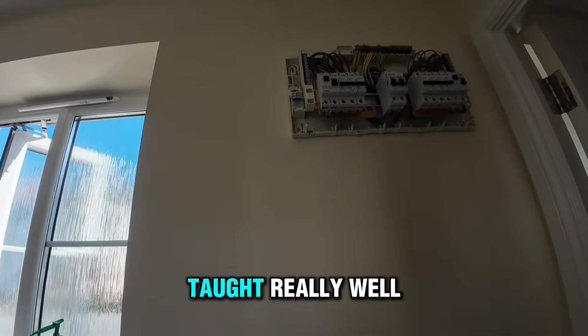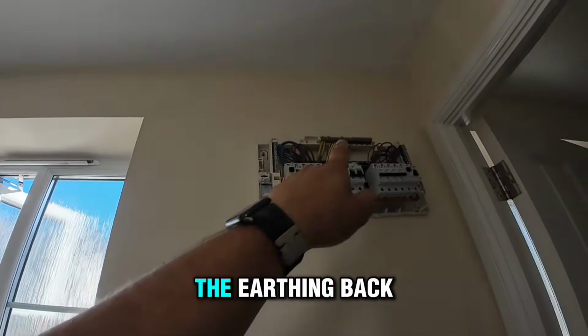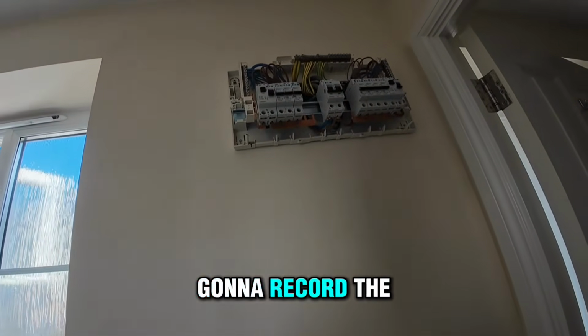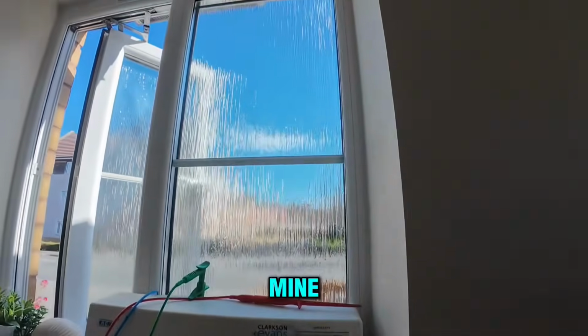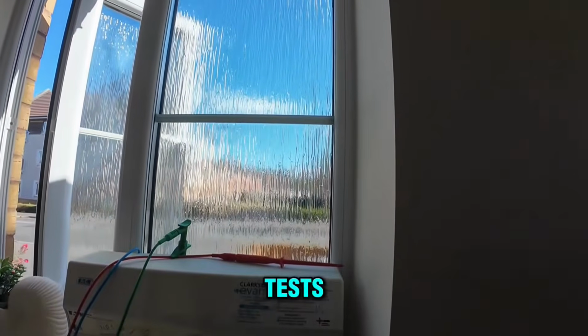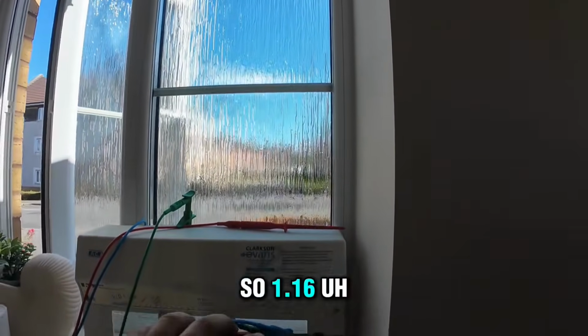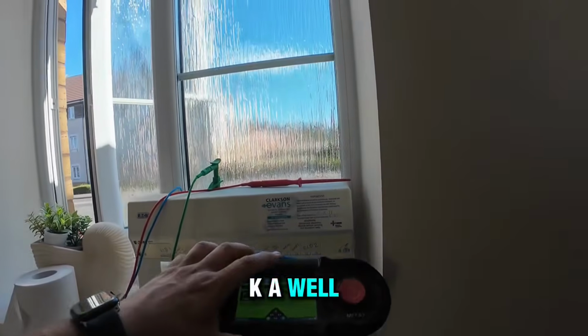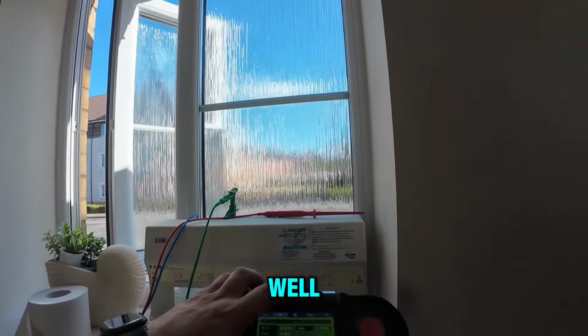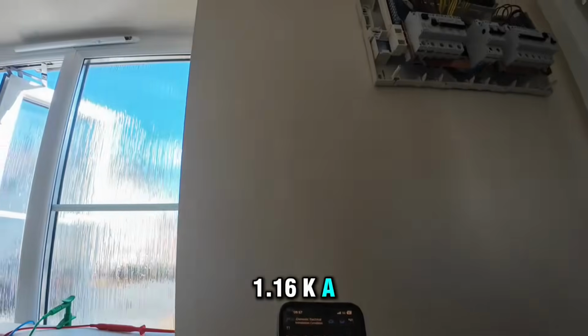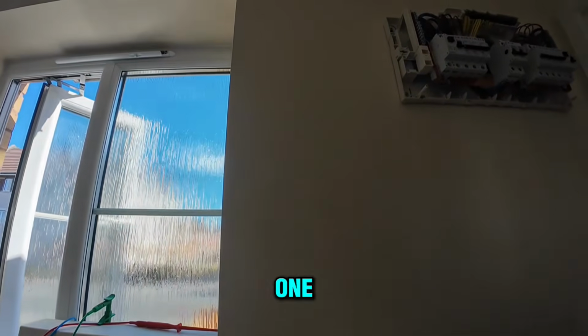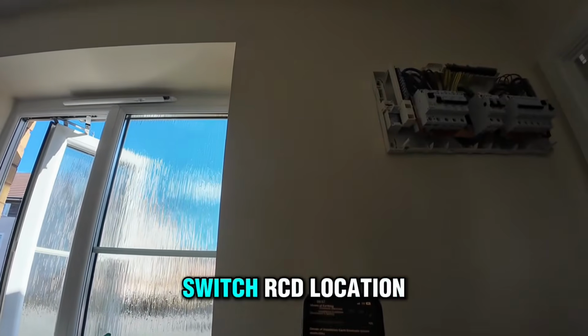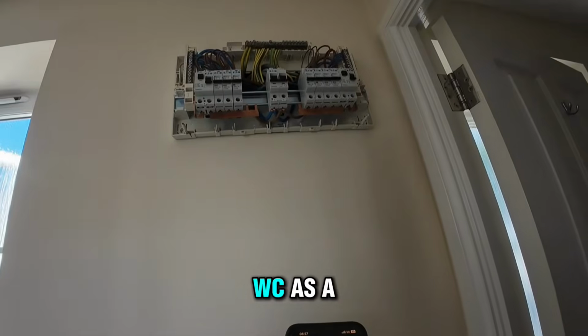If you were taught really well, you're going to put the earthing back in and then record the value. If you've got a meter like mine, it remembers your tests, so 1.16 kA. Actually, it tells you what you have to do as well. 1.16 kA. Off we go to the next one. Means of earthing, distributor's facilities. We don't have an electrode. Main switch RCD. Location WC.